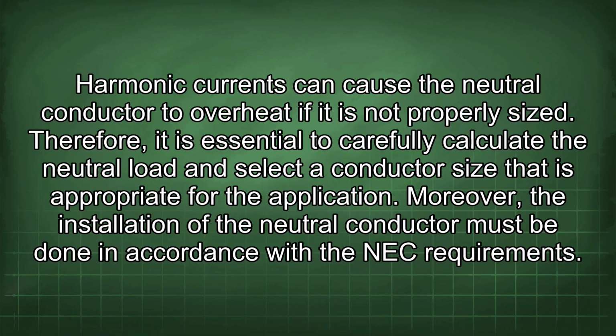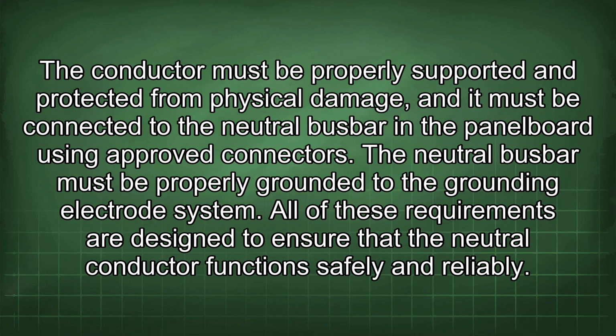application. Moreover, the installation of the neutral conductor must be done in accordance with the NEC requirements. The conductor must be properly supported and protected from physical damage, and it must be connected to the neutral busbar in the panel board using approved connectors. The neutral busbar must be properly grounded to the grounding electrode system. All of these requirements are designed to ensure that the neutral conductor functions safely and reliably.